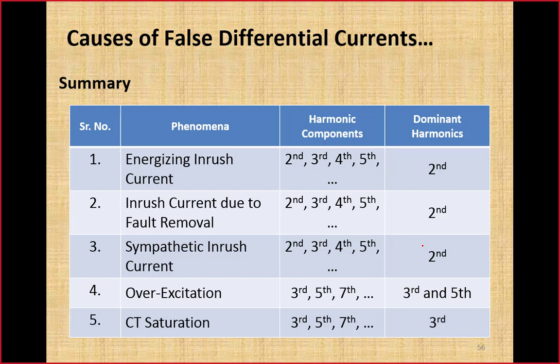So here in this table we can see the inrush current drawn due to the energization. It has all harmonic components present, and second harmonic will be the dominant one. Second phenomenon, inrush current due to fault removal. Its nature is similar to that of the inrush current drawn due to energization. So all harmonics will be present, and second will be dominant.